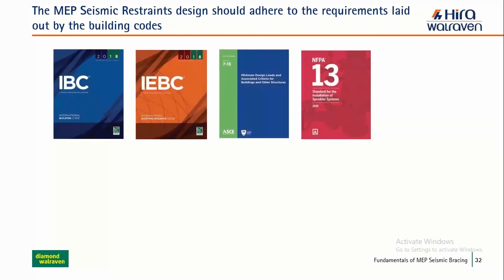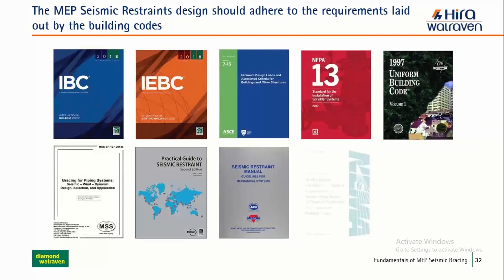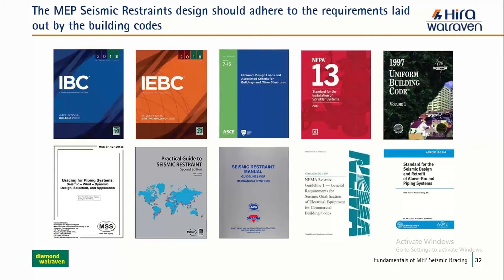When designing a seismic restraint system, several standards must be considered. The main standards include: International Building Code (IBC), International Existing Building Code, American Society of Civil Engineers (ASCE), NFPA, and Uniform Building Code (UBC). Some projects require UBC, some require IBC — both must be considered based on specification. Additionally, seismic restraint standards from ASHRAE, SMACNA, NEMA, and ASME are used for designing any seismic system for non-structural components.